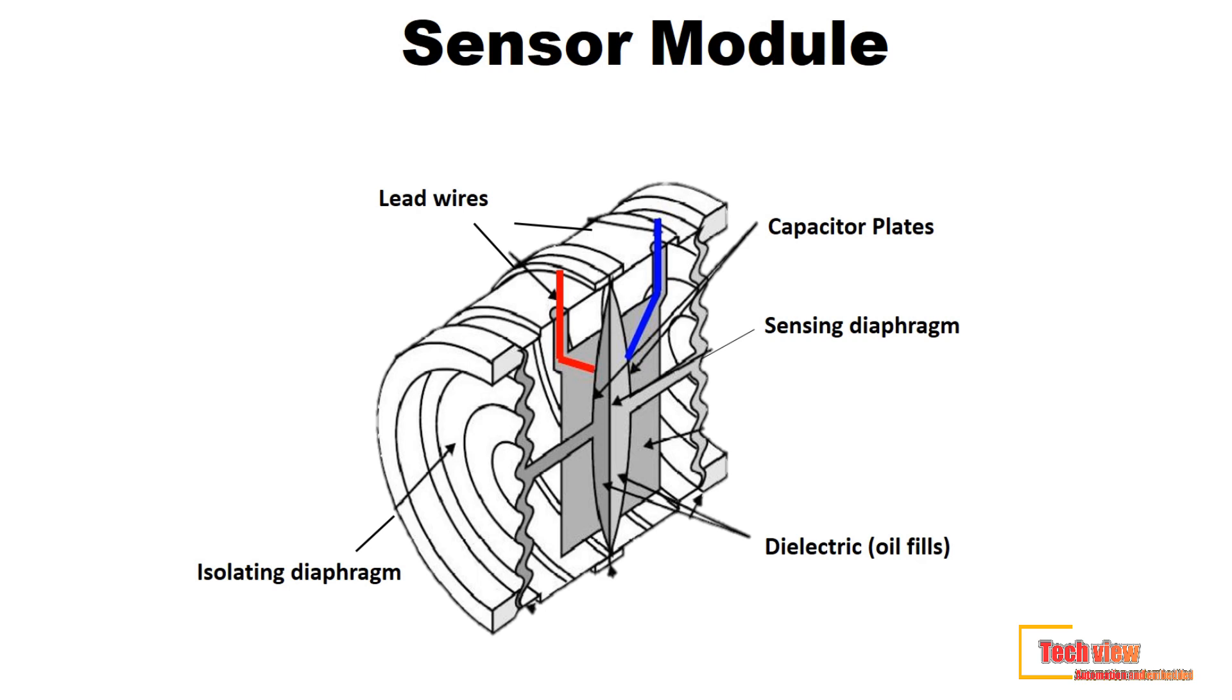Pressure applied to capacitive cells will produce a change in the capacitance of the sensor. This change will affect the oscillator frequency, and the pressure transmitter will detect this change. Then the transmitter translates this data into a standard output signal that we can read.